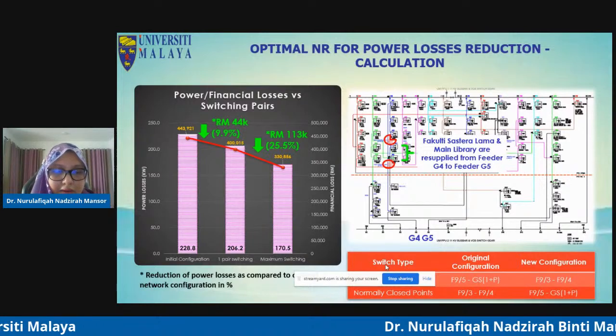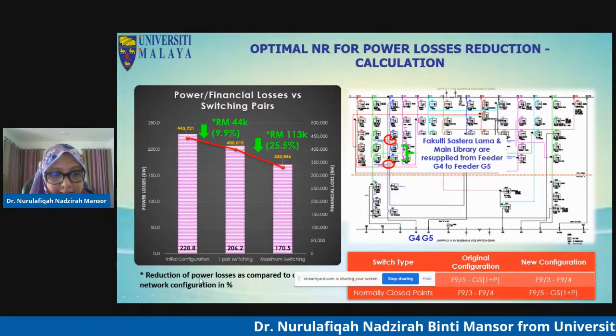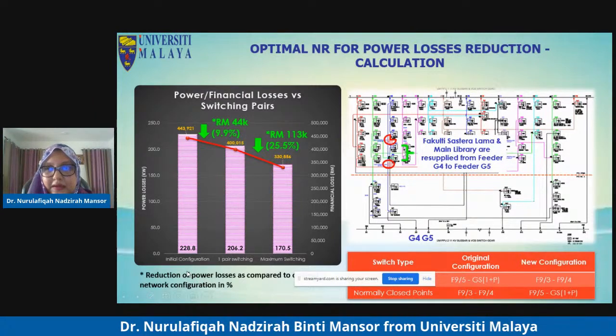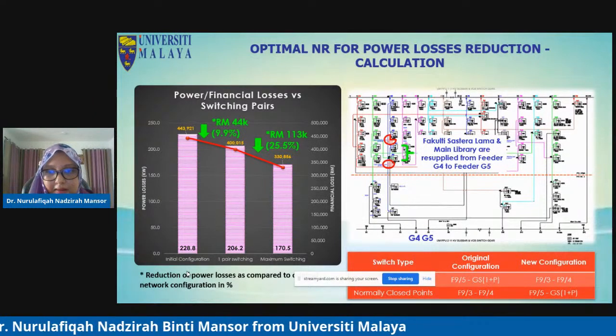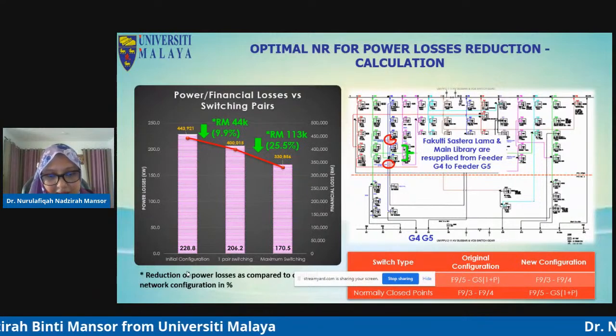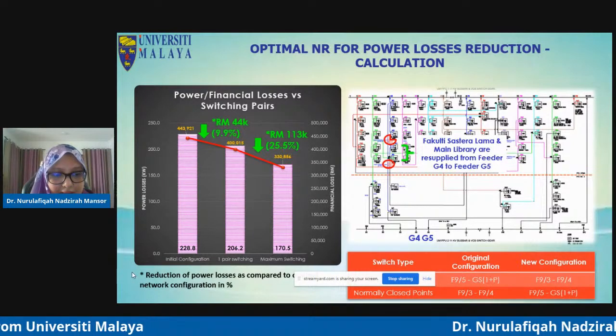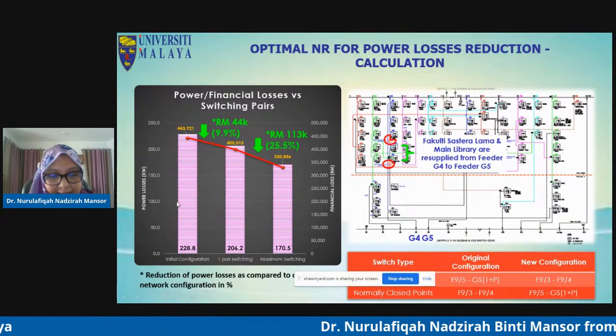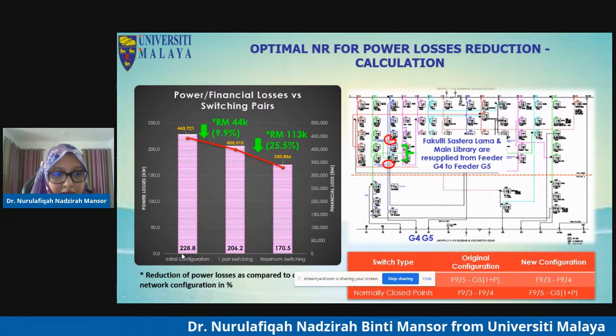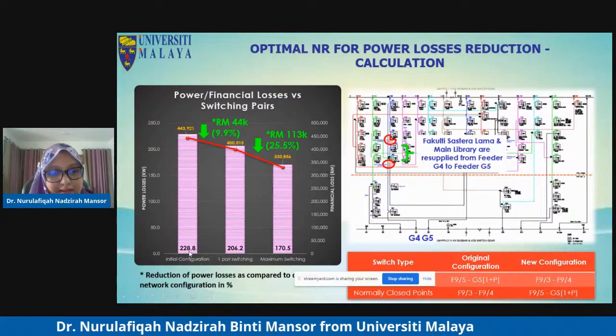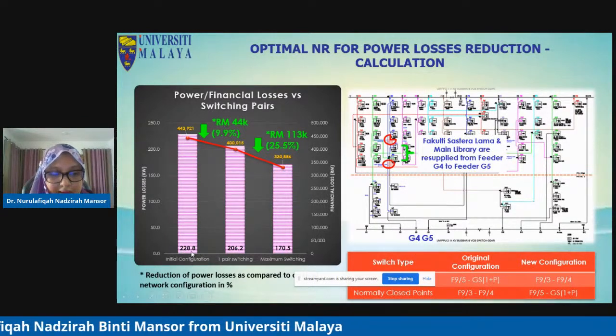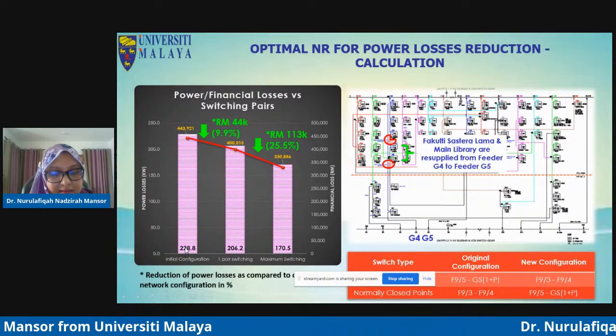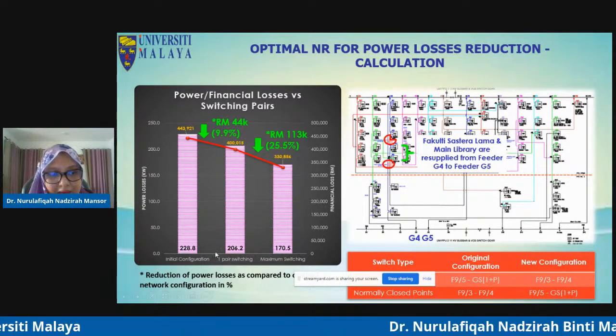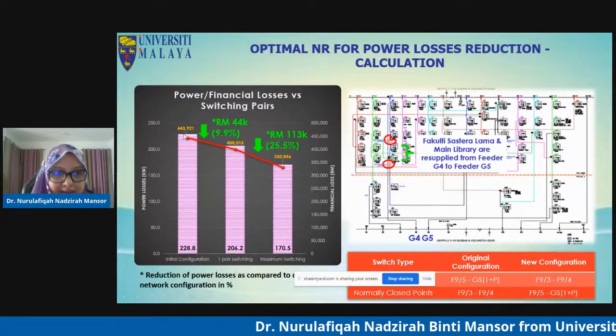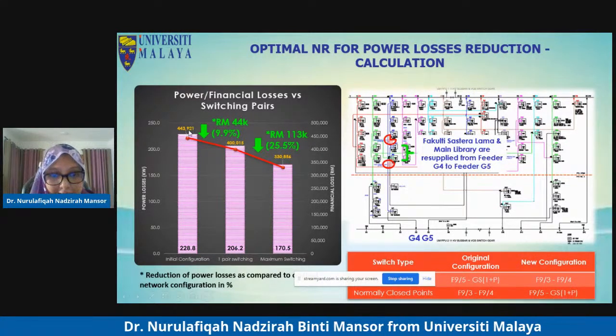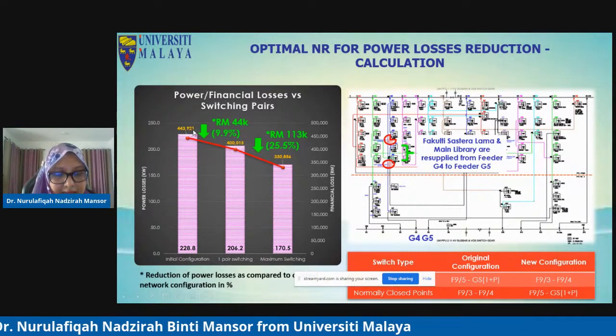So basically, this was what we presented to them. For initial configuration, if we did nothing to the network, it stays in its original configuration. We found from our modeling and calculation that the power losses would amount to 229 kilowatt at any time. If we assume a 12 hour working period, this amount of power losses would translate to RM 444 thousand financial losses in a year.